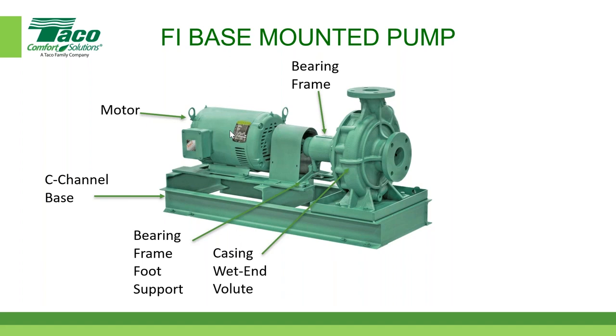Most of our pumps go out with a Baldor motor. That's our house motor. There were other options, but for the most part, it's a Baldor motor. And Taco recommends that these motors, especially 5 horse and above, have Aegis rings, which are internal rings built into the motor that help the grounding and prevent stray currents from destroying the bearings. Okay, so under normal circumstances, if you order a pump with a motor from Taco, it is going to come with these rings in there.